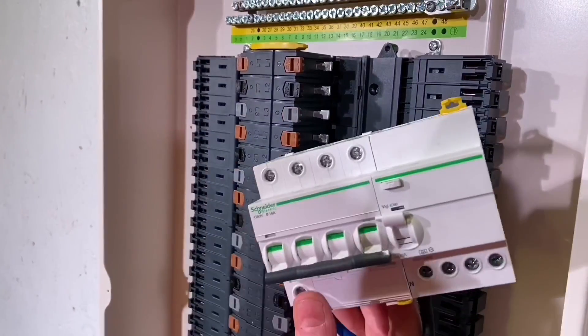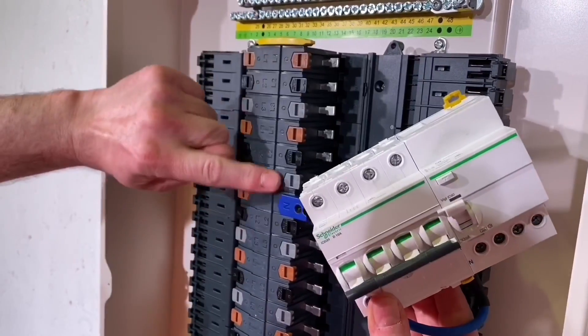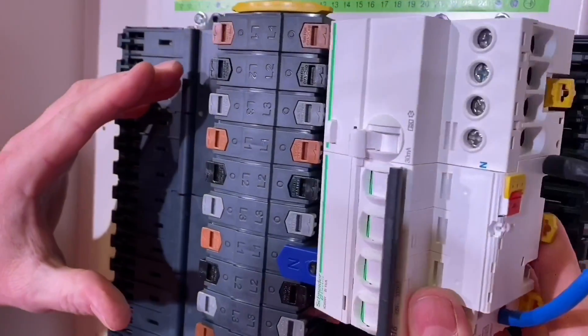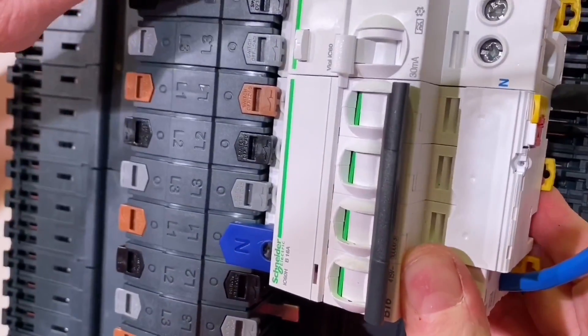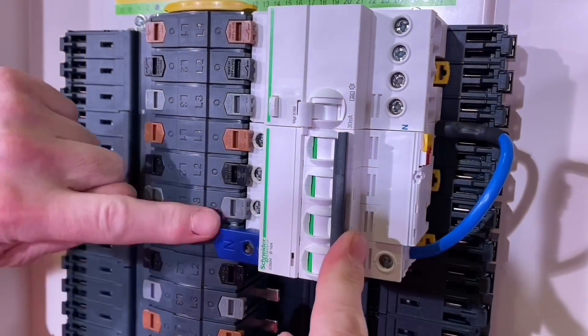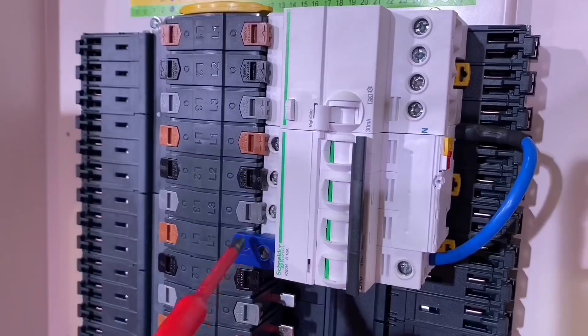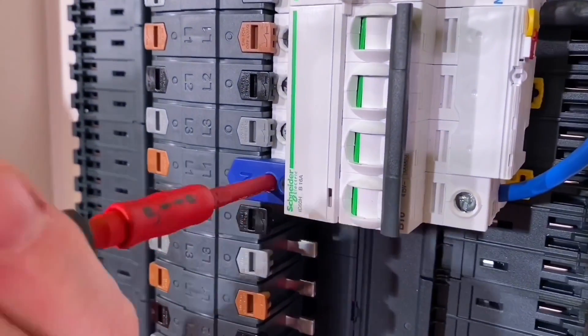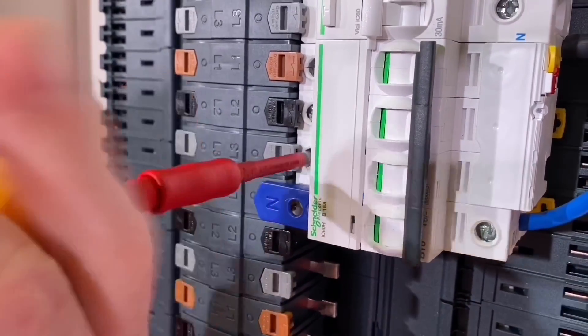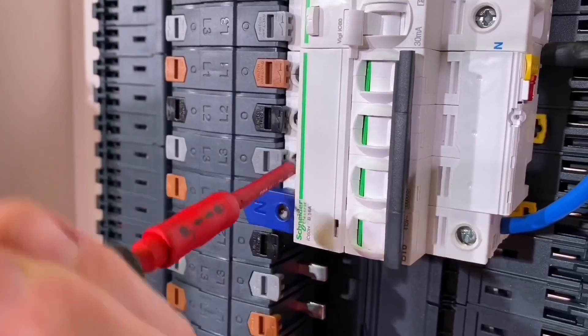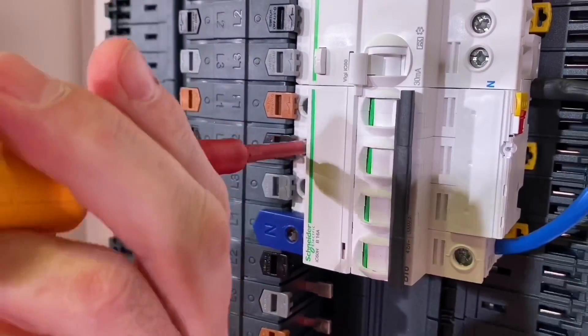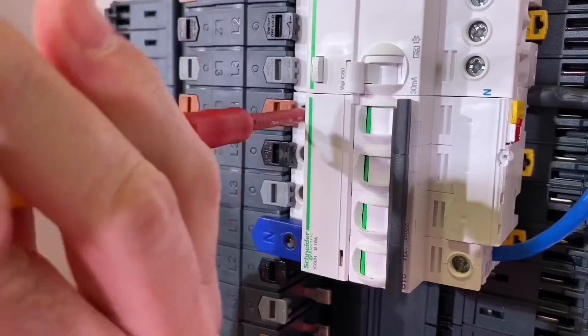There we go, last one in. We're going to fit our breaker and RCD. We'll come back to this at some point. Really important tip now Gordon, it's for fitting it. You're going to get them underneath the Isobar tabs. If you don't get them underneath you won't be able to slide the tabs across to live the breaker once it's fitted. Slight angle going in, pushed it back into position. All it requires now is again returning the screws to required torque setting. Get those cranked up and then we can slide across the fixings if we want to at that stage, but I think just get those tight first and then we're ready to move to the next stage.